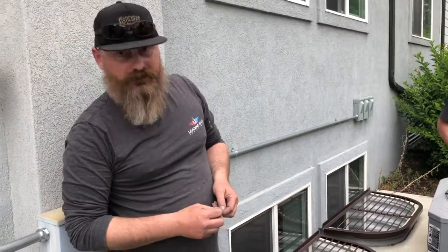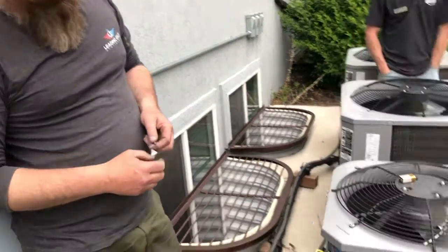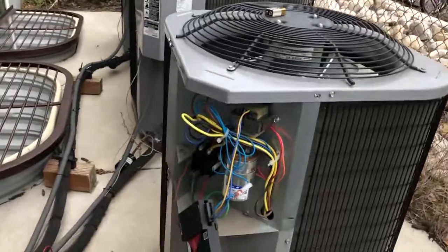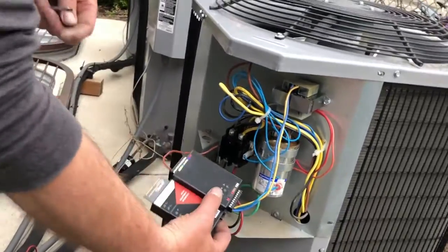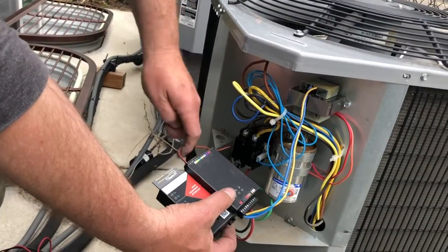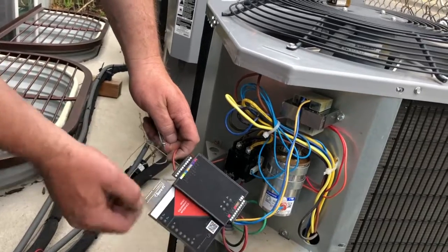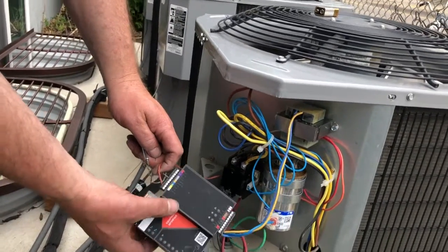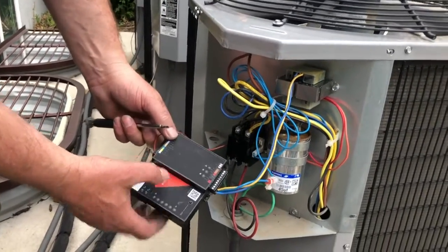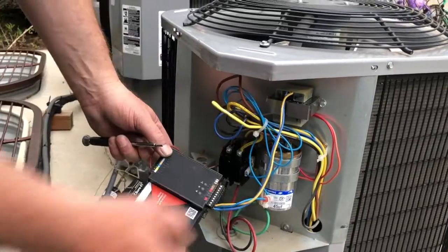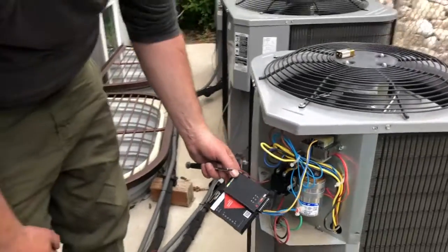We put the interface in on the contactor. We have to get the common side in here, and then the other side of the contactor on the Y terminal in here. Then we had to put a step-down transformer to power up this interface. So far everything's looking good.